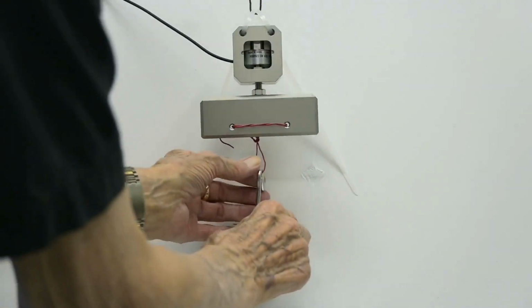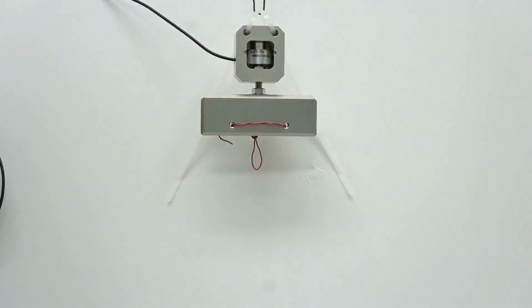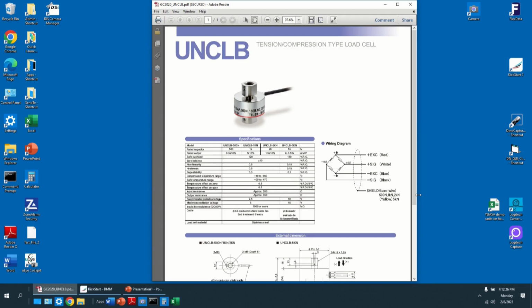Before we start the calibration, let's look at the spec sheet for the UNCLB load cell. Note the wiring diagram. The device is basically a bridge. There are 5 wires. One wire is a shield. The red wire takes 5 volts DC to the load cell. The blue wire is the negative side of the 5 volts. The white wire is the plus output. The black wire is the minus output.